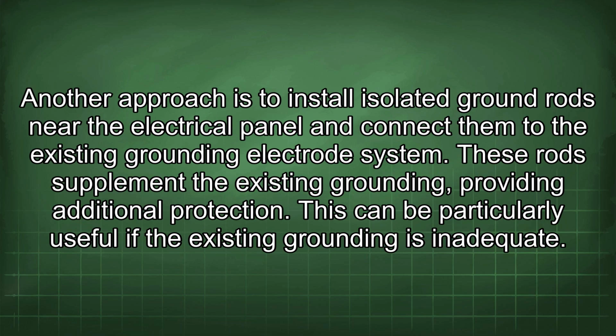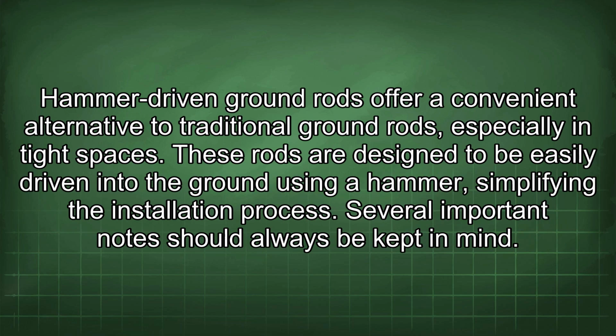Another approach is to install isolated ground rods near the electrical panel and connect them to the existing grounding electrode system. These rods supplement the existing grounding, providing additional protection. This can be particularly useful if the existing grounding is inadequate. Hammer-driven ground rods offer a convenient alternative to traditional ground rods, especially in tight spaces. These rods are designed to be easily driven into the ground using a hammer, simplifying the installation process.